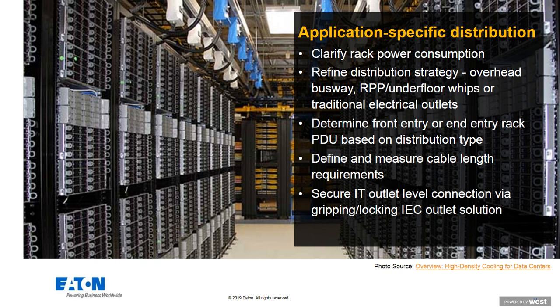You don't want a situation where you have a lot of excess cabling. Whether it be on top of the rack or underfloor, you don't want rolls or bundles of cable sitting there. The more you have there, the more it obstructs airflow. The more clutter in the way, the harder it is to work in the environment. So ideally, you want to keep those cable lengths sufficient to reach where you need to get to, but without extra that creates some sort of excess.